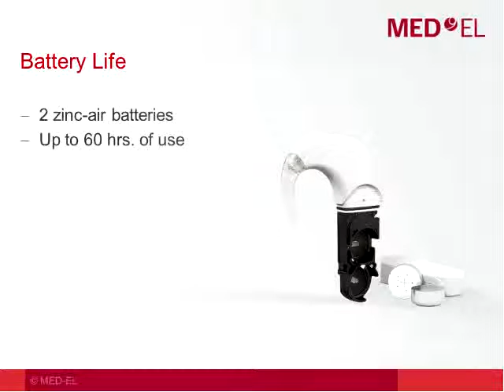The SONNET audio processor just takes two batteries. They look a lot like hearing aid batteries. They're the larger size. They're a size 675, and the ones that last the longest are zinc air batteries. And for cochlear implants, we always recommend that you use the high power zinc air batteries, because that will give you more consistent power and longer battery life. With the SONNET processor, you should get up to 60 hours of use with just two of those zinc air batteries.